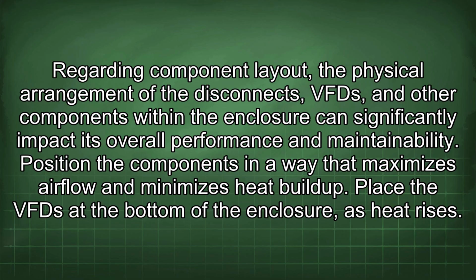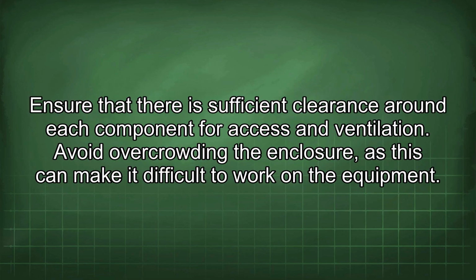Position the components in a way that maximizes airflow and minimizes heat buildup. Place the VFD at the bottom of the enclosure as heat rises. Ensure that there is sufficient clearance around each component for access and ventilation. Avoid overcrowding the enclosure, as this can make it difficult to work on the equipment.